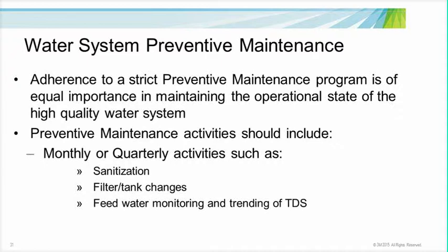A healthy PM, or preventive maintenance, schedule will also include semi-annual and annual activities. These more long-term interval activities include RO unit inspection and servicing, measurement system calibration, for example conductivity meters, flow meters, and if you have an inline pH meter, the calibration of those systems. And then lastly, just an example, distribution pump operation and inspection, replacement or inspection of those wear components such as the O-rings and/or gaskets.